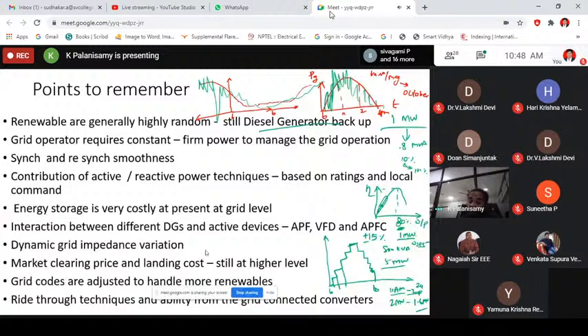So what will happen? The VFDs, the correction capacitors, or the other solar inverters connected in the same system will start to behave differently. Before you connect the APF, the active power filter, your grid impedance is different. The source impedance seen by the VFD or the solar inverter may be different, but when you suddenly connect an active power filter, the grid impedance will vary. If you are not taking care of that dynamics in a proper way, it will lead to other issues.